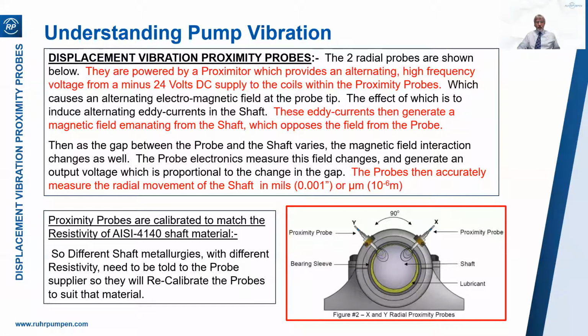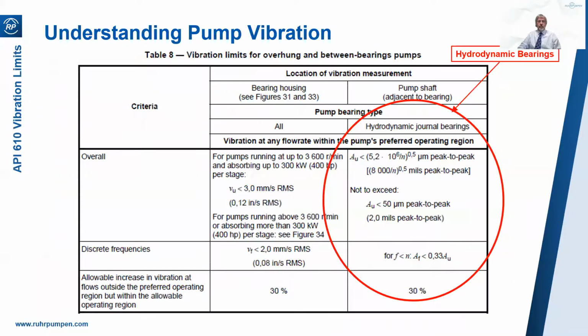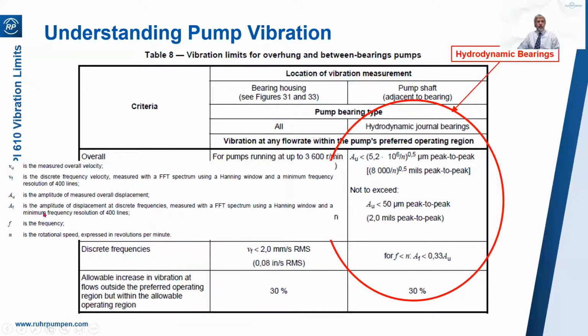If you have sleeve radial bearings and ball thrust bearings, then you'll have proximity probes for the sleeve bearings, and for the ball thrust bearings, you'll have accelerometers. But if you have sleeve radial bearings and a tilting pad type thrust bearing, then you'll have another proximeter reading in the Z direction on the non-drive end of the shaft. So here, measuring in that direction instead of that direction. Here are the vibration limits for sleeve and tilting pad bearings. And here on the left is the key. You see we've got the amplitude, and it's a function of the speed of the pump. And that's going to give you the answer in peak to peak micrometers, or here in mils.